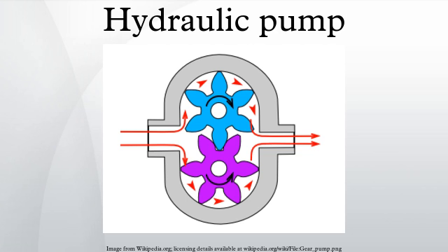Another positive attribute of the gear pump is that catastrophic breakdown is a lot less common than in most other types of hydraulic pumps. This is because the gears gradually wear down the housing and/or main bushings, reducing the volumetric efficiency of the pump gradually until it is all but useless. This often happens long before wear causes the unit to seize or break down.